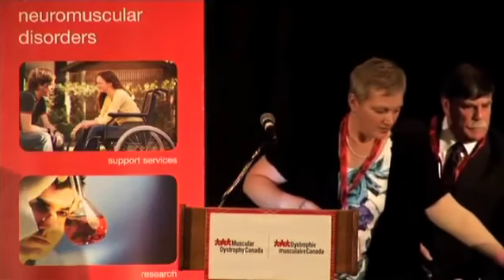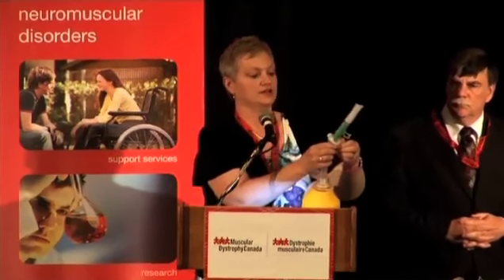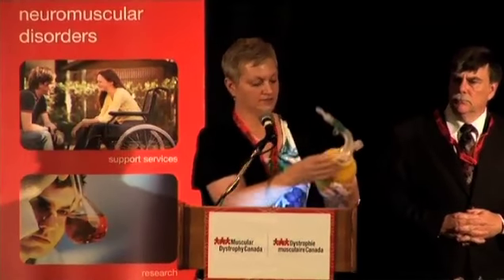So then we have lung volume recruitment and breath stacking. And I know that you saw some video and things today about it. This really is and can be your best friend, okay? Very simple piece of equipment, and what it has is the resuscitation bag, and we have on it not for resuscitation, that is very important. Then there's simply a piece of flex tubing. Inside this green piece is a one-way valve, so that when you squeeze the bag, the air only goes into your patient. The next piece is called a valve trap. So if for any reason the valve was dislodged, it would be stopped at the next valve piece.